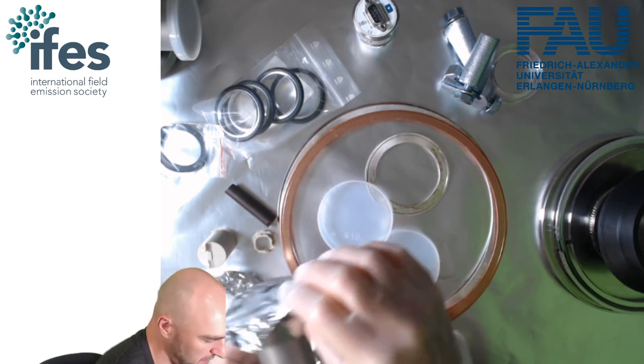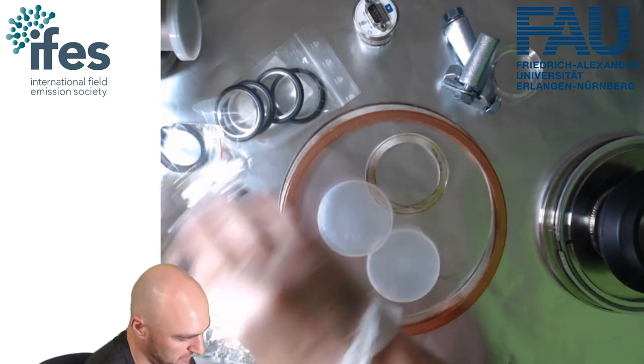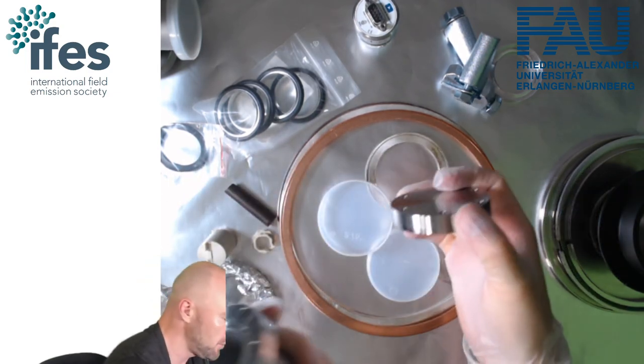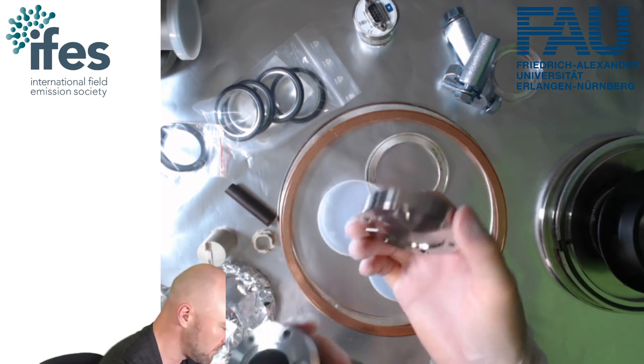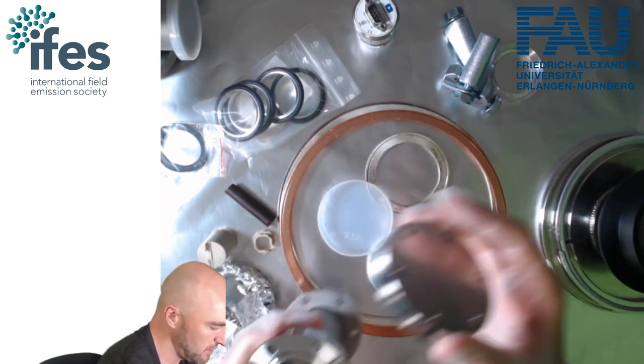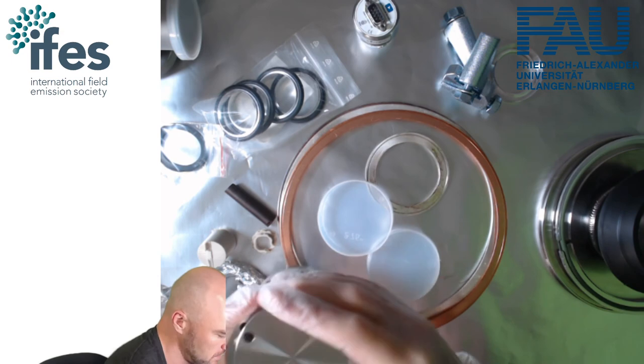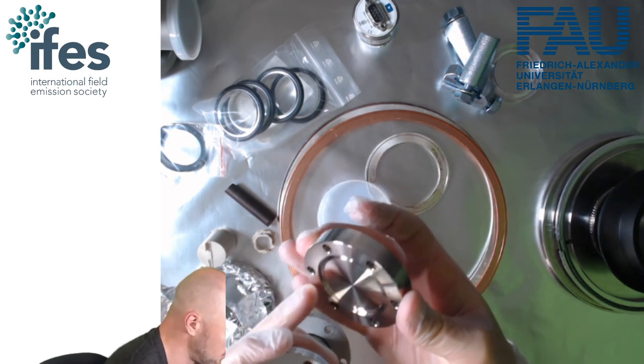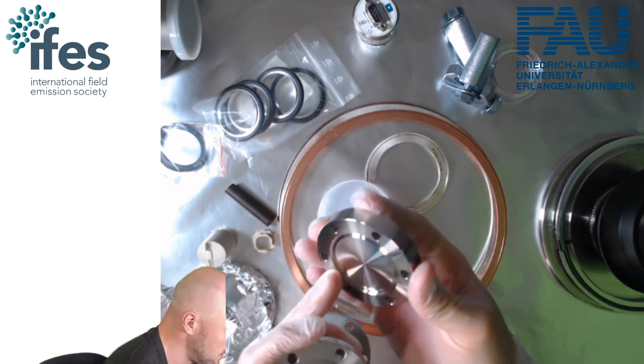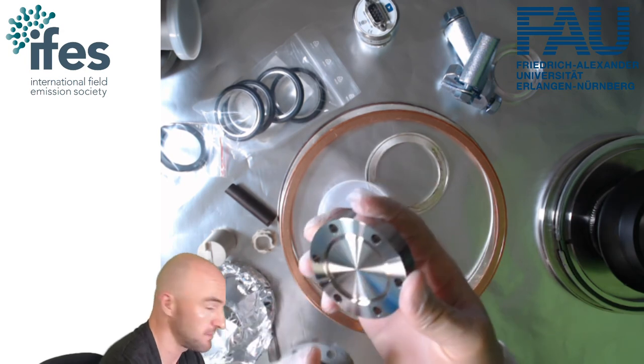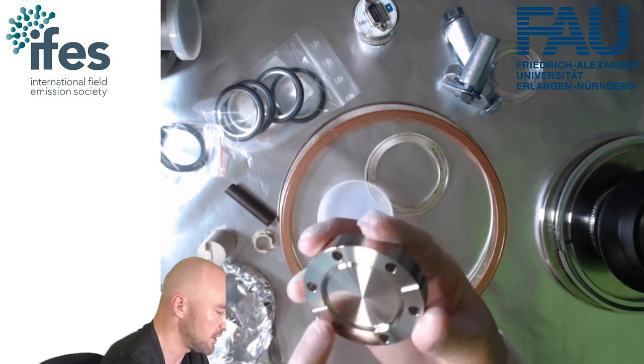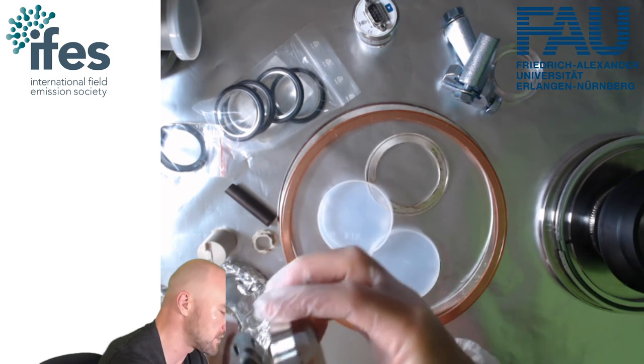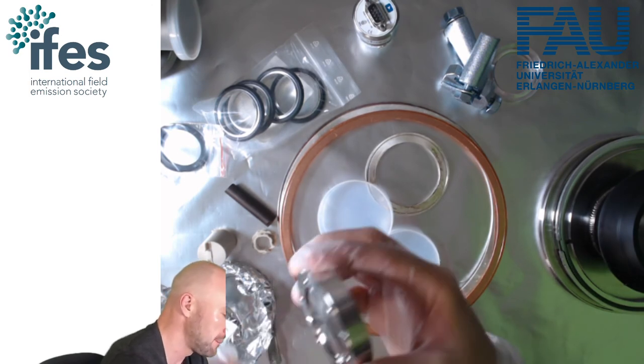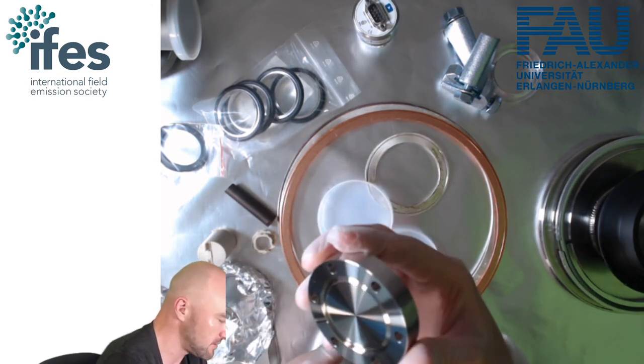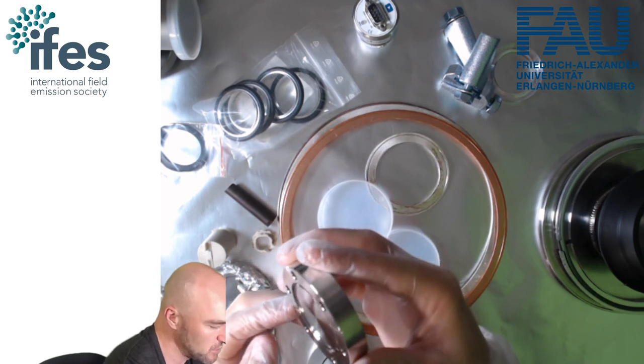And here we have a typical CF flange part. And if you want to put those together, so I don't have a CF40 gasket here right now, what you need to do is you need to look at where the leak detection grooves are. Sorry, I haven't explained those before. So those CF flanges, they have grooves on them, and the grooves, they're supposed to be vertical. Yeah? And the reason why they exist is because you use them for leak testing.